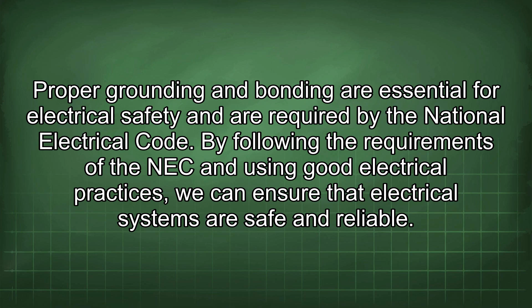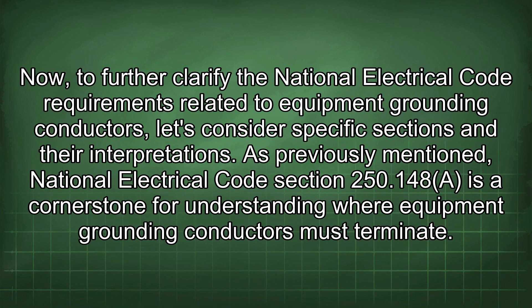By following the requirements of the NEC and using good electrical practices, we can ensure that electrical systems are safe and reliable. Now, to further clarify the National Electrical Code requirements related to equipment grounding conductors, let's consider specific sections and their interpretations. As previously mentioned, National Electrical Code Section 250.148 is a cornerstone for understanding where equipment grounding conductors must terminate. This section mandates that equipment grounding conductors be run with the circuit conductors and terminate in the equipment grounding bus within the panel board.